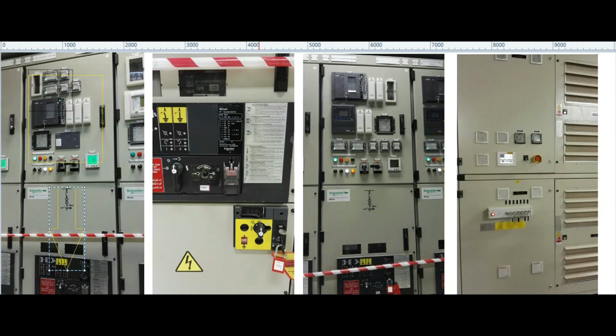In the second snap you can see this is the circuit breaker module. This circuit breaker is in test position, and this is the earth switch. Earth switch position is on. That means earth switch is connected with the ground, and this is locked with a padlock. There is also lockout tagout system implemented at site, because this is again during commissioning stage.